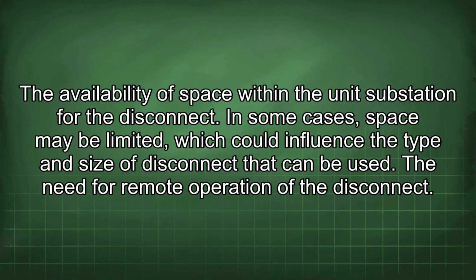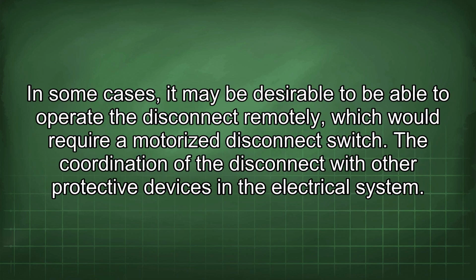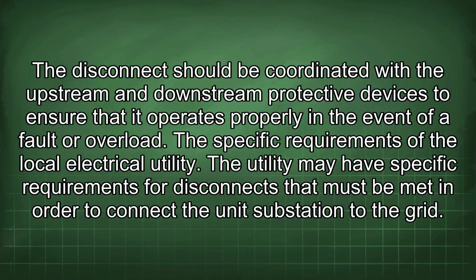The availability of space within the unit substation for the disconnect. In some cases, space may be limited, which could influence the type and size of disconnect that can be used. The need for remote operation of the disconnect. In some cases, it may be desirable to be able to operate the disconnect remotely, which would require a motorized disconnect switch. The coordination of the disconnect with other protective devices in the electrical system. The disconnect should be coordinated with the upstream and downstream protective devices to ensure that it operates properly in the event of a fault or overload.